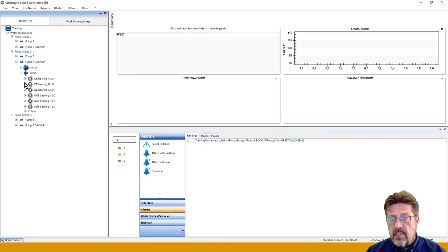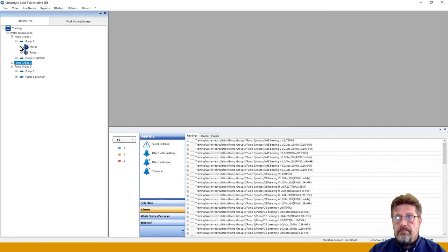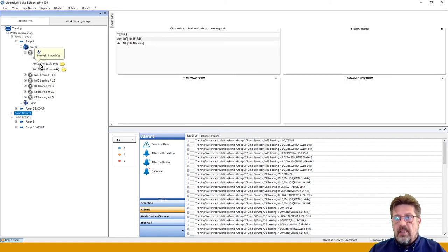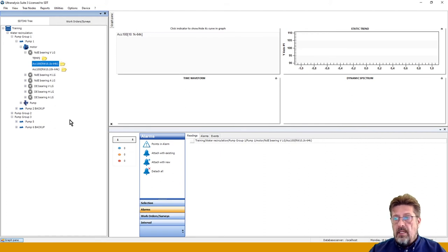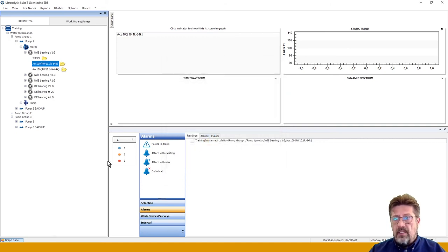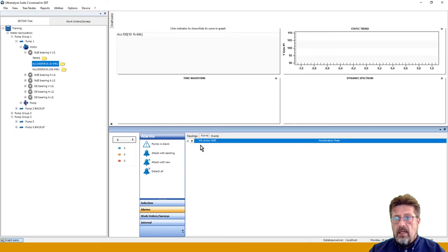So let's put some alarm on a vibration. Because there is a possibility to make a small mistake, and I just want to help you with that. So you can see acceleration 10 hertz to 1 kilohertz 64. So let's see what we have in the bank. So set alarm from template. Yes, we have one for that. So we can assign it with no problem. I will assign alarm, and here it is. So that's my alarm. I can assign many more alarms in the same way you just assigned this one, but not two alarms on the same indicator. So you cannot have two alarms monitoring peak on the same machine, because those are then conflicting data. You can have one monitoring peak, another one monitoring crest factor, RMS velocity, RMS acceleration.